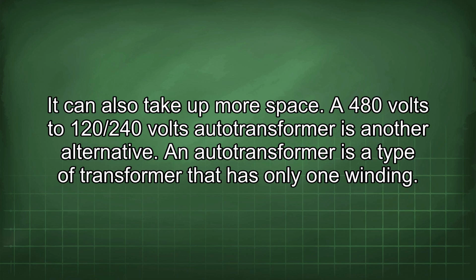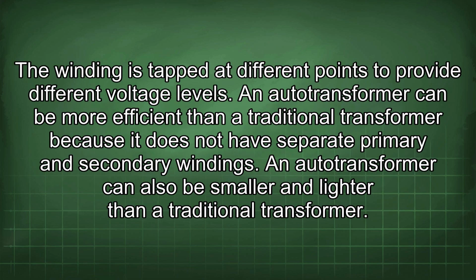A 480 volts to 120/240 volts autotransformer is another alternative. An autotransformer is a type of transformer that has only one winding. The winding is tapped at different points to provide different voltage levels. An autotransformer can be more efficient than a traditional transformer because it does not have separate primary and secondary windings. An autotransformer can also be smaller and lighter than a traditional transformer.